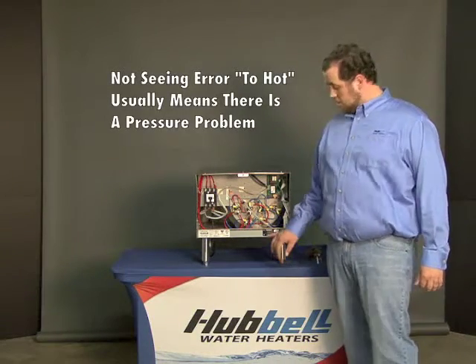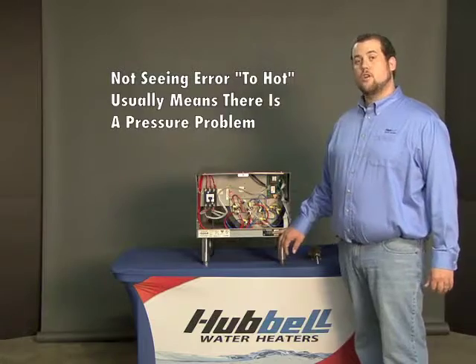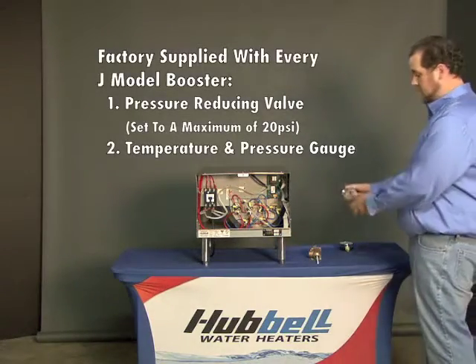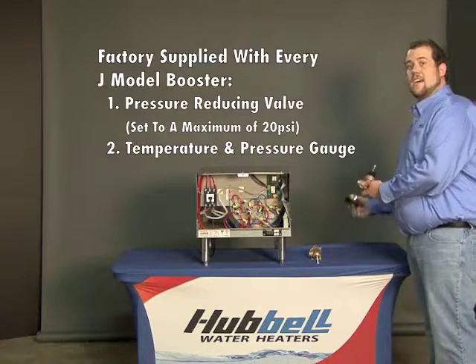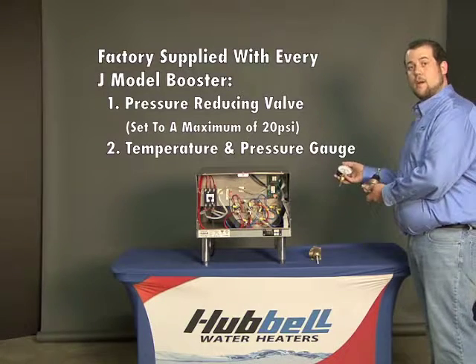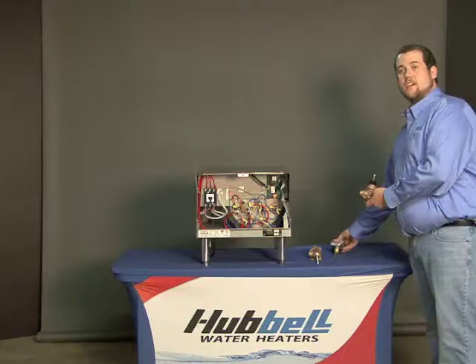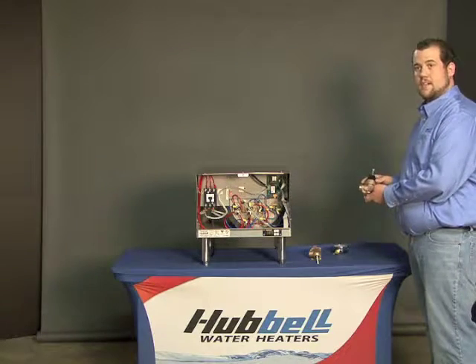Not seeing an error too hot flashing on the display, in all likelihood it is a pressure problem. Supplied with the Hubbell booster heater is a pressure reducing valve and a temperature and pressure gauge. The pressure should be set to a maximum of 20 psi. If it is anything other, please set the PRV to 20 psi.